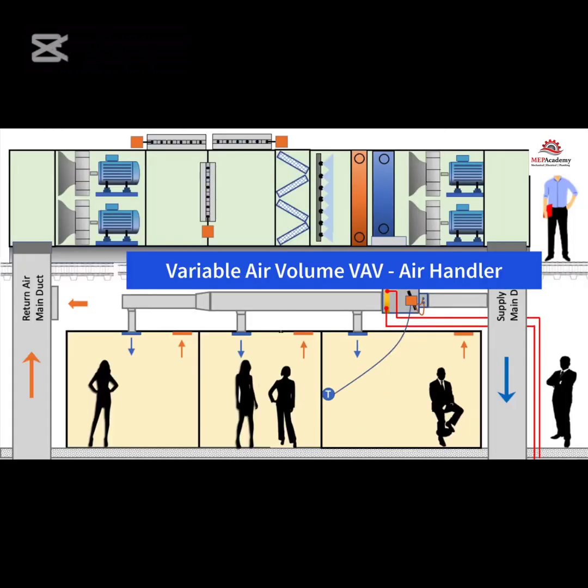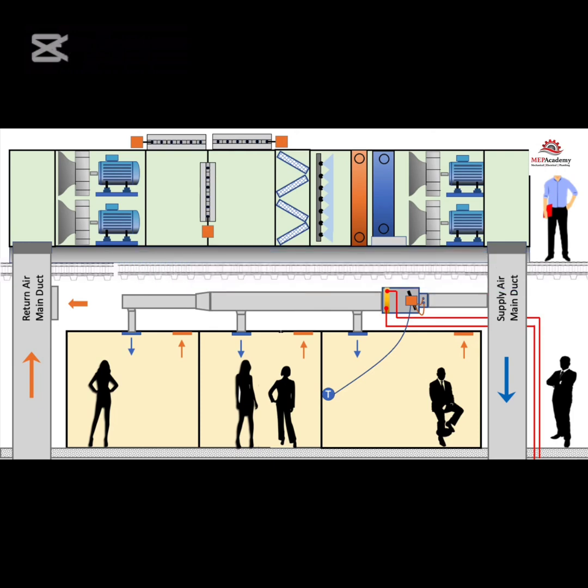Here is a variable air volume (VAV) air handler mounted on a roof. The VAV air handler is probably the most common system used in medium to large commercial buildings. This custom air handler starts with the return air section, then travels through the return air fans. The air next enters the economizer section, where the air can be exhausted out of the building or returned to the system.